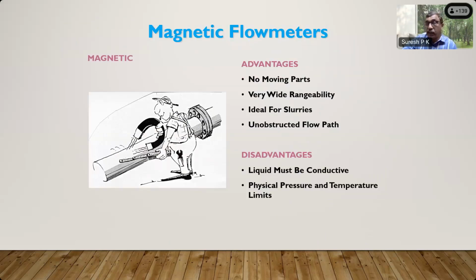The advantage is that there are no moving parts in that. It creates no pressure loss, very wide rangeability. Obstruction is not there. Ideal for slurries. It is easy for maintenance. Disadvantage is liquid must be conductive. If the liquid is not conductive, the conductor has to pass through the meter to measure it. So if the liquid is not conductive, then it will not measure. Let's say, for example, DM water, demineralized water, which is not conductive, so it will not measure. You have to add some salt into it or something like that to make it conductive. Then only it will measure. The physical pressure and temperature limits are also there for magnetic flow meters.